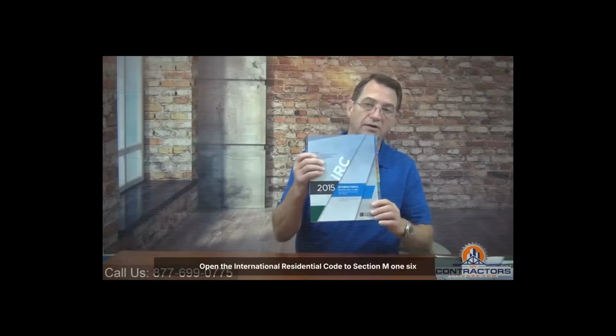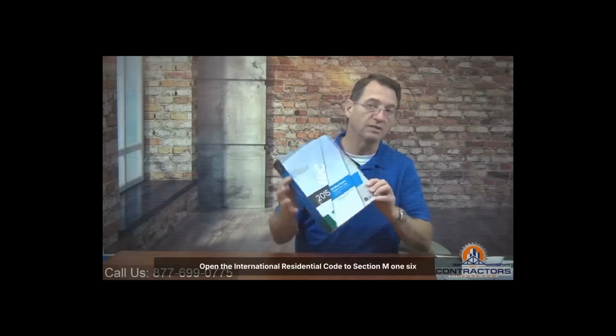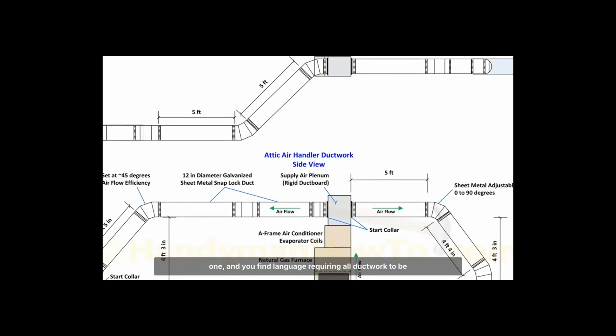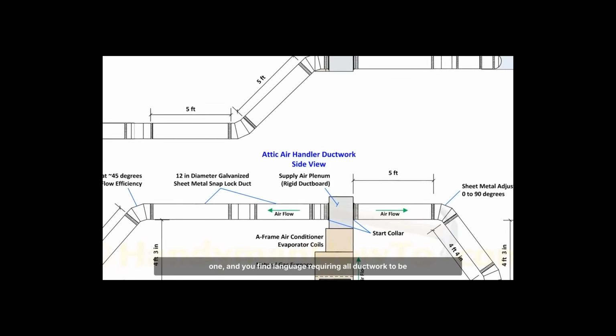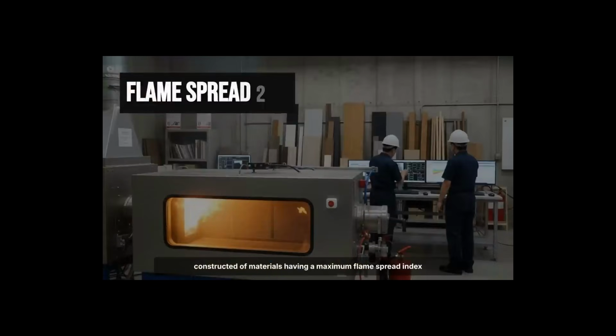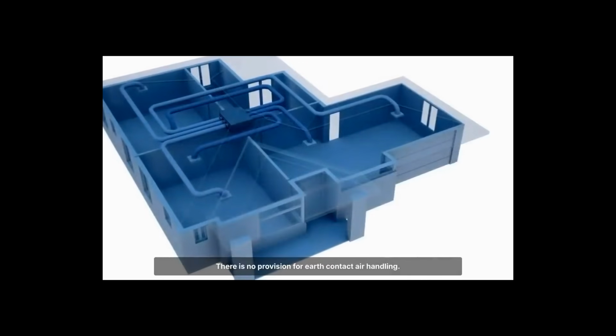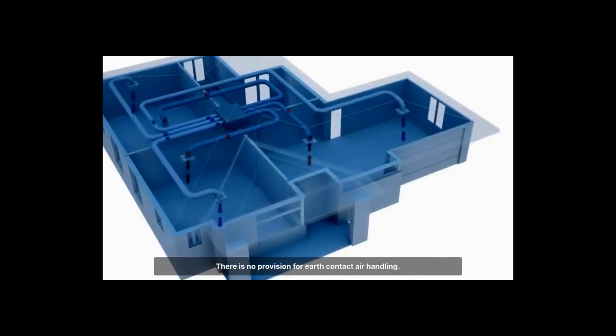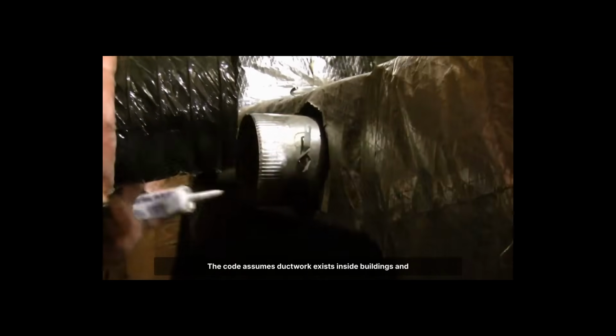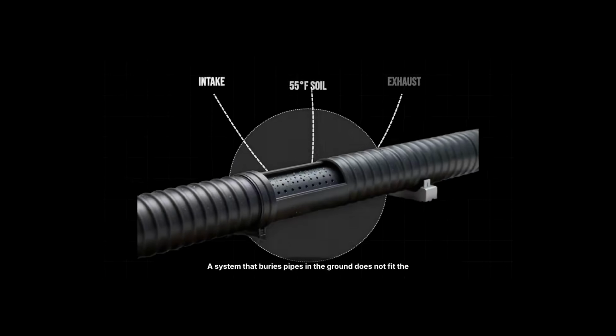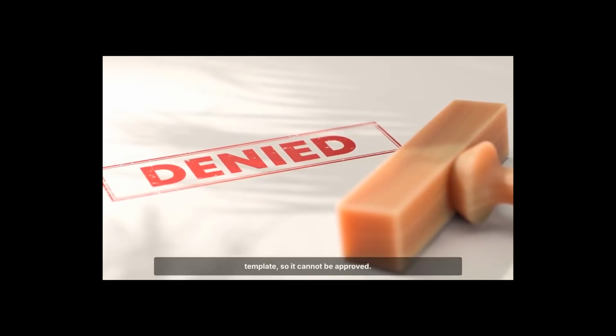Open the International Residential Code to section M1601 and you find language requiring all ductwork to be constructed of materials having a maximum flame spread index of 200. There is no provision for earth contact air handling. The code assumes ductwork exists inside buildings and nowhere else. A system that buries pipes in the ground does not fit the template, so it cannot be approved.